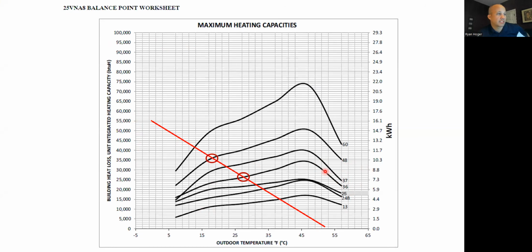I follow how much capacity my unit can make, and where it crosses the load of my building, in this case 27 degrees. At 27 degrees and below, my heat pump can't make enough heat to heat my building anymore. So this triangle over here, it can't handle it. It's doing this, but I need that. So below 27 degrees is when my electric resistance supplemental heat would kick on and help the heat pump out. But if I have a dual fuel system, I don't do that. I shut off the heat pump and I turn on the fossil fuel system.